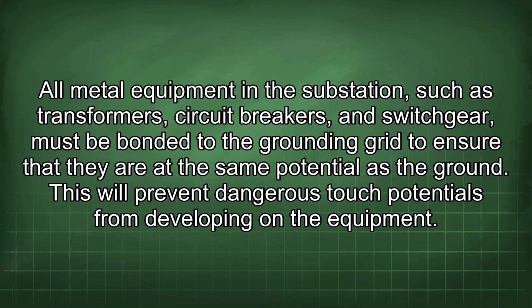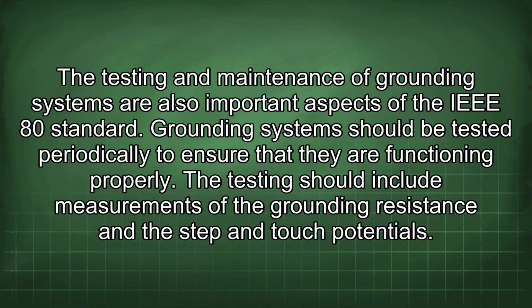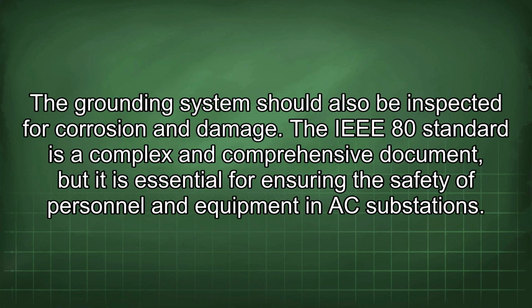All metal equipment in the substation, such as transformers, circuit breakers, and switchgear, must be bonded to the grounding grid to ensure that they are at the same potential as the ground. This will prevent dangerous touch potentials from developing on the equipment. The testing and maintenance of grounding systems are also important aspects of the IEEE standard. Grounding systems should be tested periodically to ensure that they are functioning properly. The testing should include measurements of the grounding resistance and the step and touch potentials. The grounding system should also be inspected for corrosion and damage.